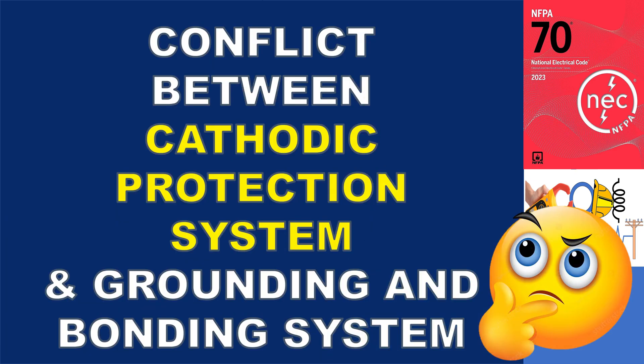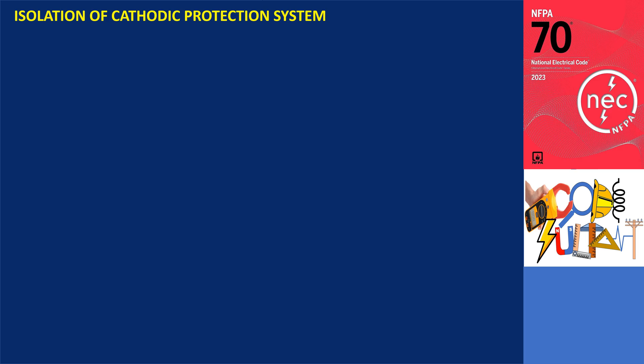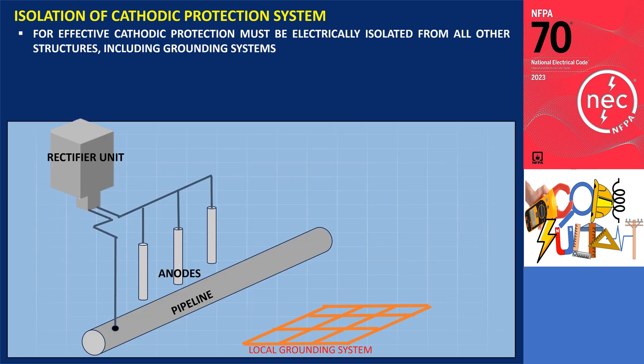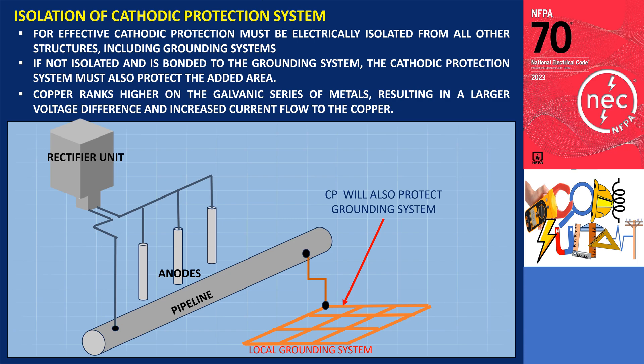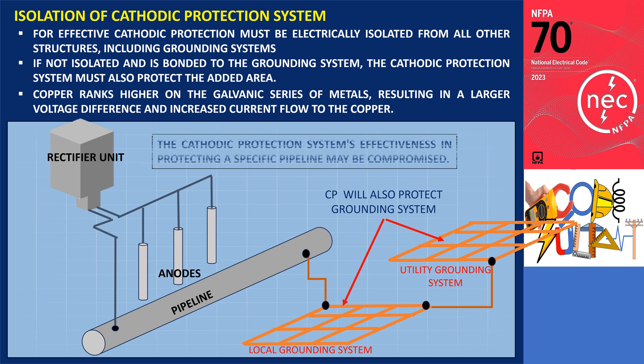While cathodic protection is vital, it can conflict with another important requirement: safety grounding and bonding. For effective cathodic protection, the structure or pipe being protected must be electrically isolated from all other structures, including grounding systems. If the structure is not isolated and is bonded to the grounding system, the cathodic protection system must also protect the added area. Moreover, most grounding systems employ copper, which ranks higher on the galvanic series of metals, resulting in a larger voltage difference and increased current flow to the copper. Additionally, when the grounding system is bonded to the utility grounding, the cathodic protection system also ends up protecting them. As a result, the cathodic protection system's effectiveness in protecting a specific pipeline may be compromised, leading to a shorter anode lifespan or higher rectifier output.